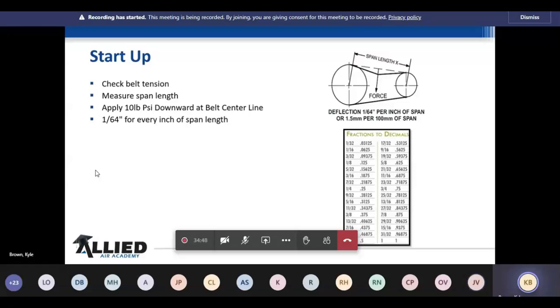And you're in danger of that spider bracket on that bearing on the blower section. That bearing that's in that spider bracket, it's going to come out. That shaft is going to pull through it. And I guarantee you, if you've got a bunch of units on that roof, if you go to another unit, the belt's going to be the same way. You can cause a lot less heartache by going ahead and setting these things up the correct way.